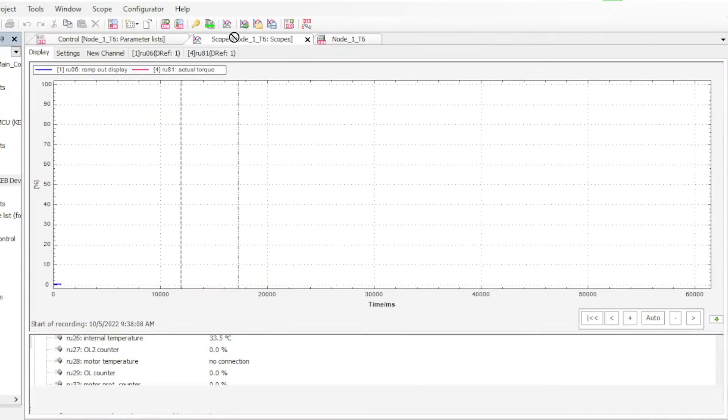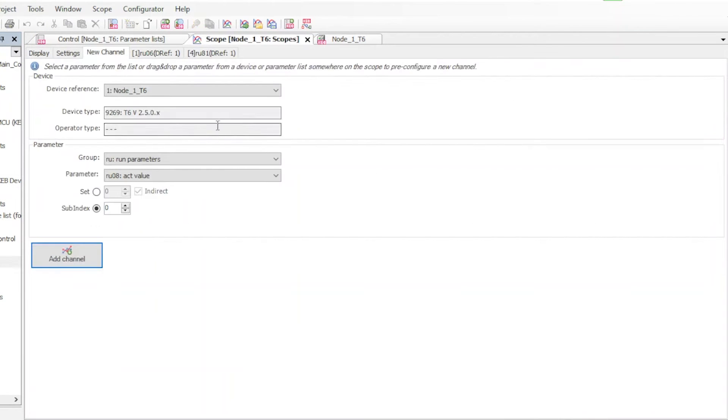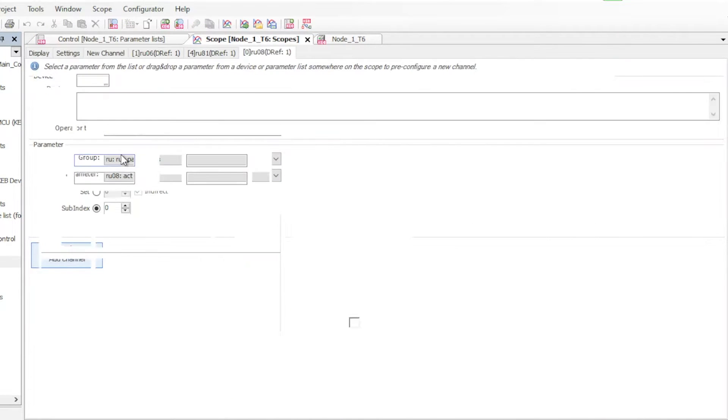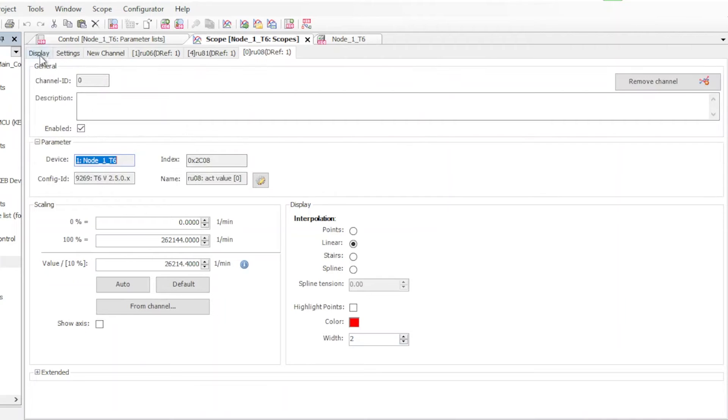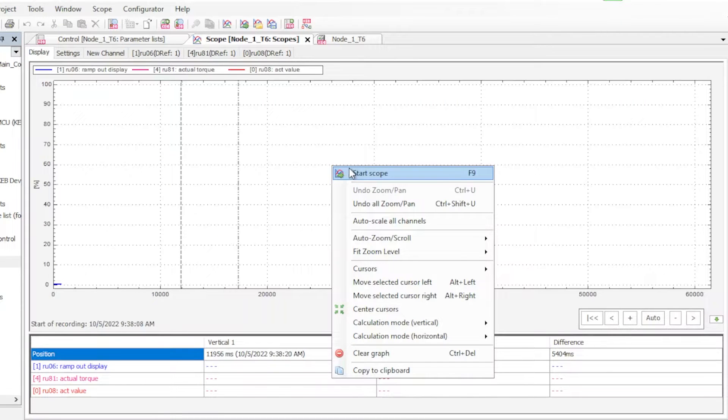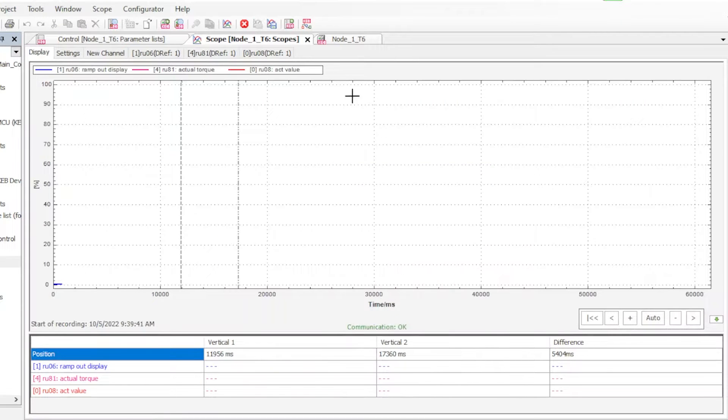The COMBIVIS scope function is a built-in oscilloscope that lets you measure and record up to 16 parameters in real time. You can measure parameters like speed, current and voltage and measure them against each other. Here we'll go into the display tab where we can click on start scope to begin the recording.